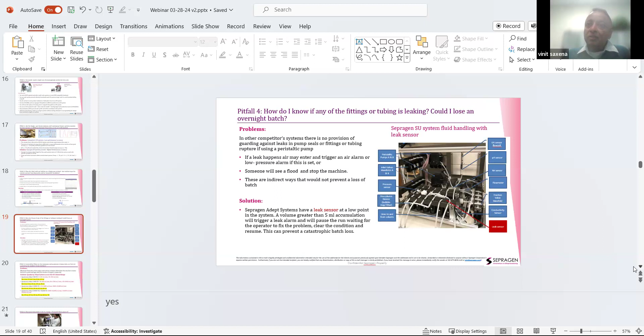So the solution is that all our systems have a low point. They have a catchment below the tubing set. And so if there's more than 3 to 5 ml of liquid that leaks, the system will give you an alarm. There's a leak sensor. The system gives an alarm and will pause for the operator to fix the problem, clear the condition, and then resume operations. So that way you avoid any catastrophic batch loss.